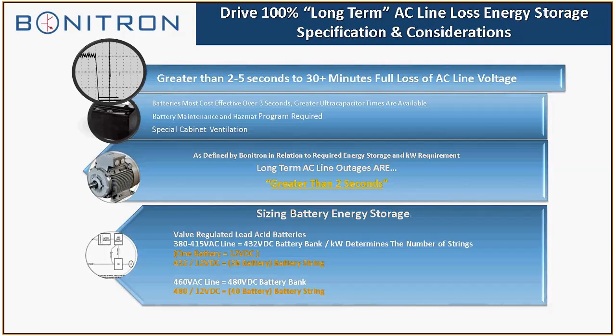Another thing to consider: if the customer is using battery energy storage, there has to be a battery maintenance and hazmat program involved. And also, if you decide to integrate batteries into your own cabinet, there are special considerations. Batteries vent gases, and the gases have to have a way to get out of the cabinet. So there's a little bit of difference between battery cabinets and regular electronic space. If you're going to do your own energy storage, hopefully you have enough information on how to set up a battery cabinet, but we can also help you with that too.